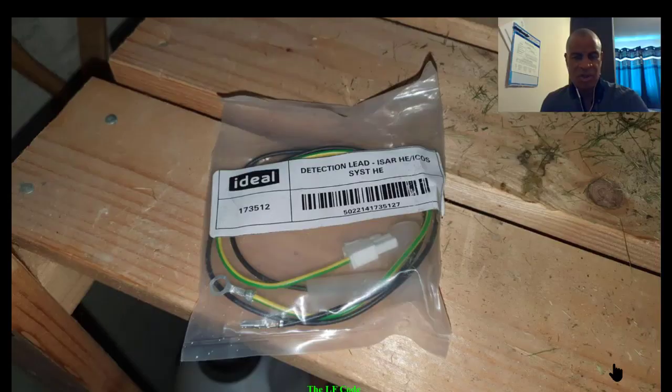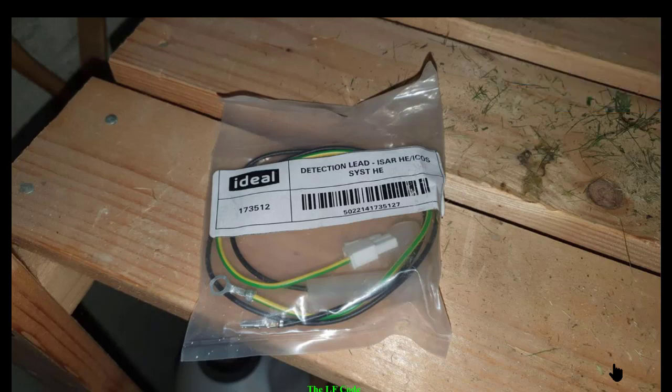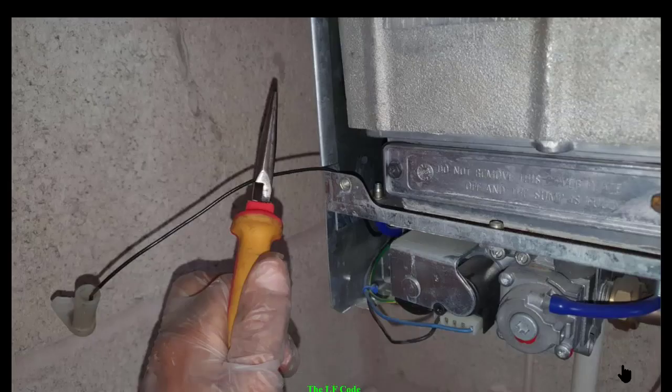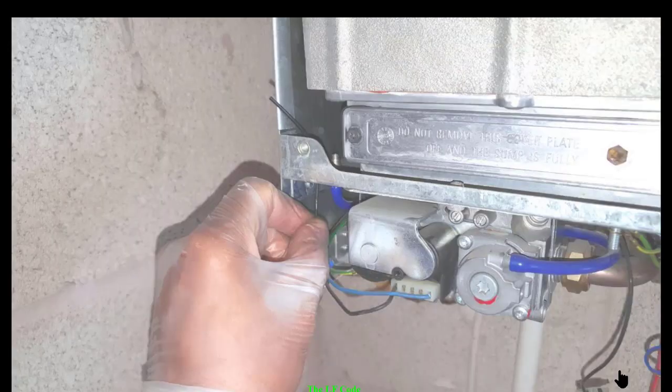Now what we're going to do, we're going to assume that that cable has broken down and we have to replace it. So I'm just going to go through how we would replace the detection lead. So what we've done here, we've pulled the plug off the electrode and we're going to cut the wire just like this. Now the reason why we're going to cut it like that is because it's got to go a specific way once we put the new one in, and you'll see what I mean. So once it's cut, then you're going to pull it through just like this downwards, and then you're going to remove the rest of the cable.